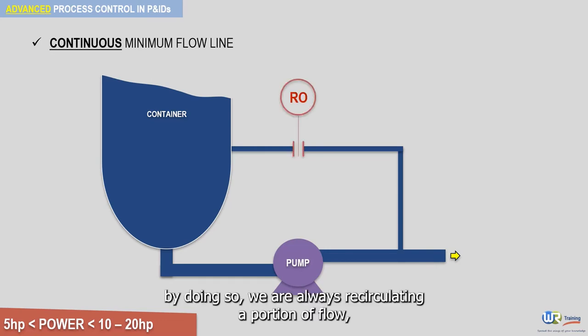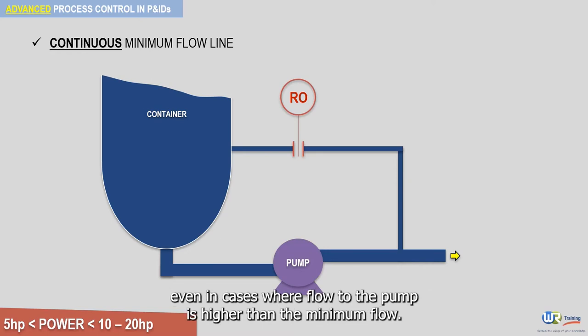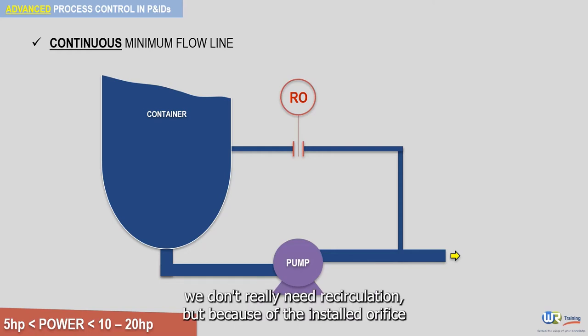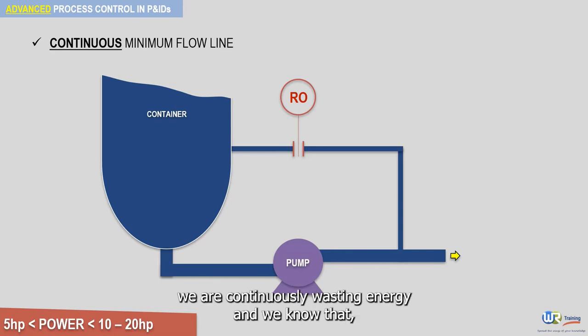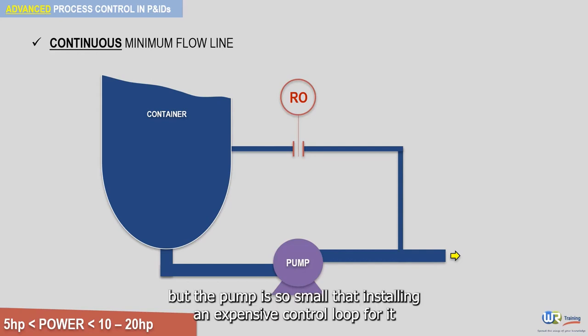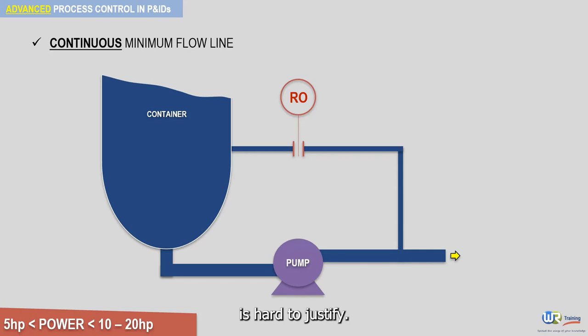By doing so, we are always recirculating a portion of flow, even in cases where flow to the pump is higher than the minimum flow. When the flow to the pump is higher than the minimum flow, we don't really need recirculation, but because of the installed orifice, we are continuously wasting energy. But the pump is so small that installing an expensive control loop for it is hard to justify.